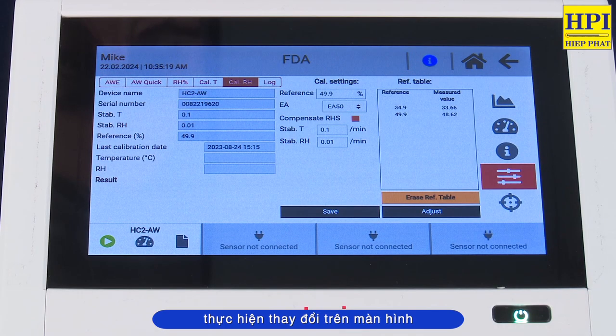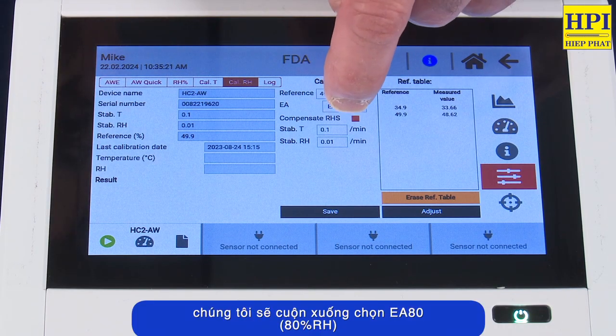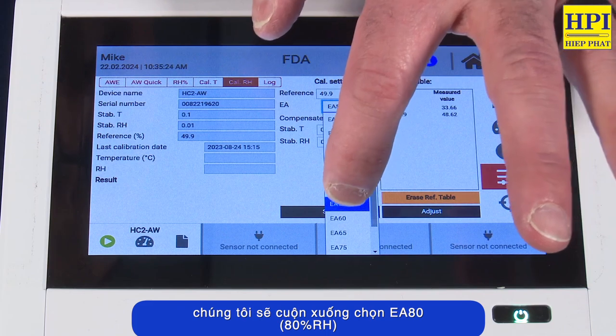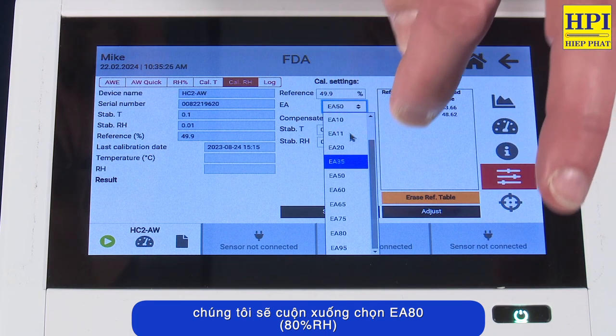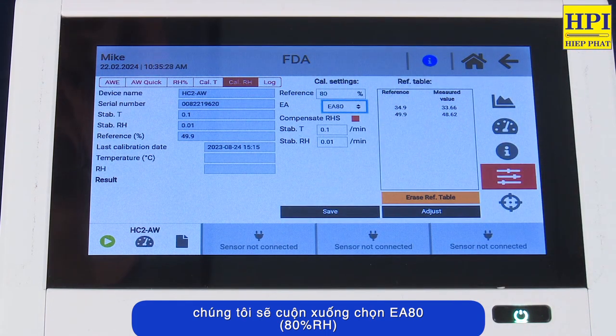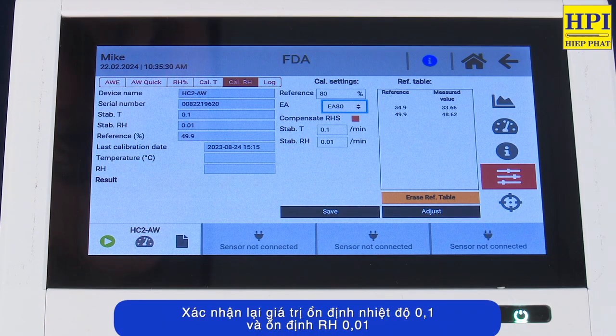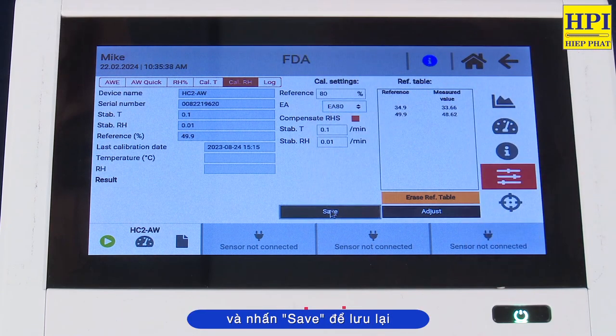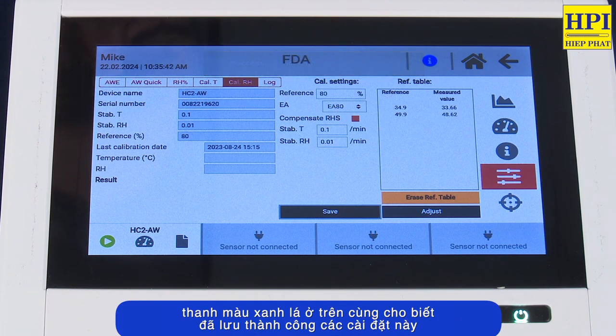We want to change the Cal settings to reflect the new humidity standard. In this case, we want to scroll. We've chosen 80% RH. We select that. We verify temperature stability, 0.1, RH stability, 0.01, and we save these settings. Again, green bar at the top indicates we've successfully saved these settings.